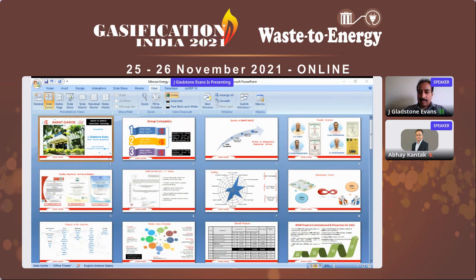The various technologies followed for waste to energy conversion can broadly be classified into 2. One is biological processing technology, and the second is thermal conversion technology. Biological processing technology is mainly composting, biomethanization, etc. And I will be concentrating on the thermal conversion technology. In that, you have incineration, gasification, pyrolysis, and pelletization. Incineration is normally used for mixed waste, for any type of waste, whether dry waste, wet waste or a combination. Gasification and pyrolysis are normally used for dry waste. And in pelletization, the dry waste is converted into pellets, further processed, and then used in a conventional boiler for certain percentages.